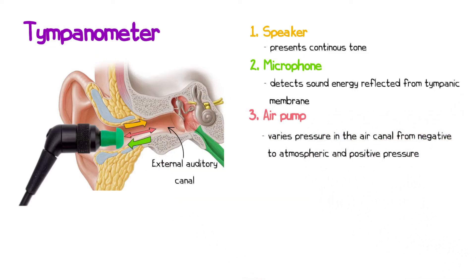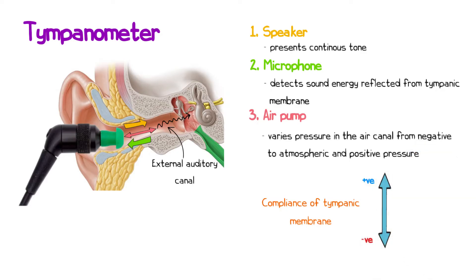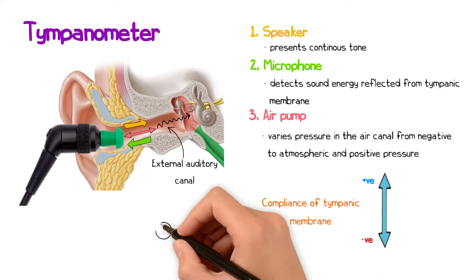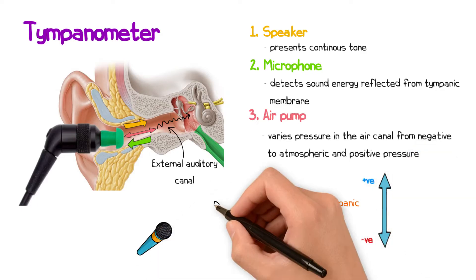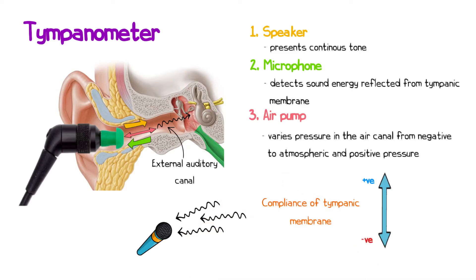As pressure in the ear canal is varied, the tympanic membrane is displaced, altering the amount of sound energy that enters the middle ear. The tympanometer measures the compliance of the tympanic membrane as the pressure sweeps from negative to positive values, using the amount of sound energy detected by its microphone to estimate the amount of sound energy admitted into the middle ear.